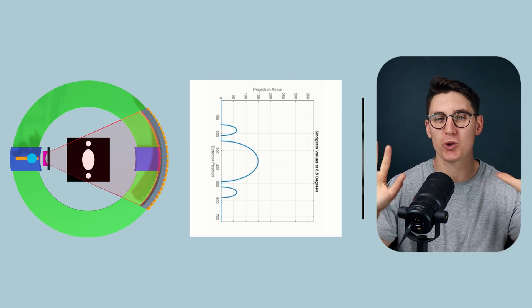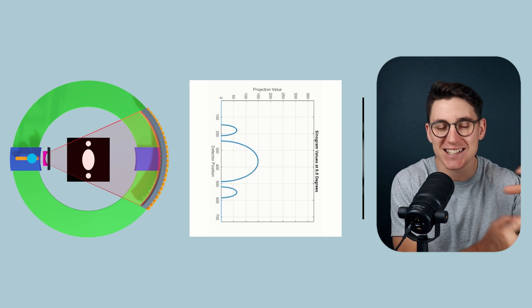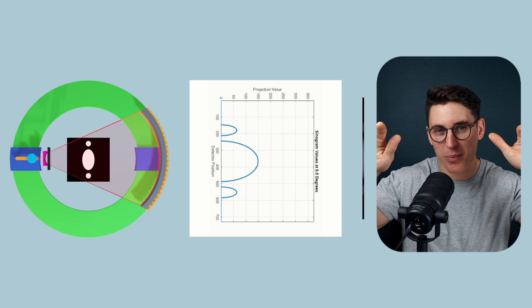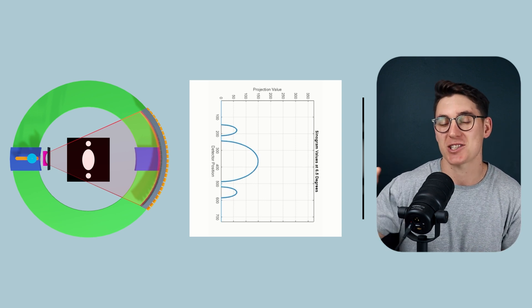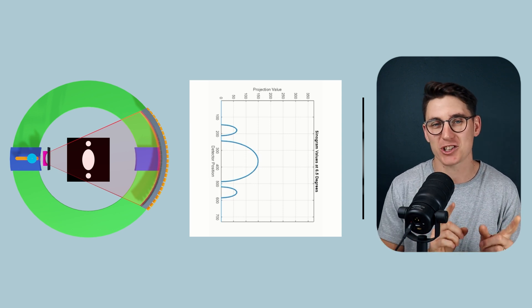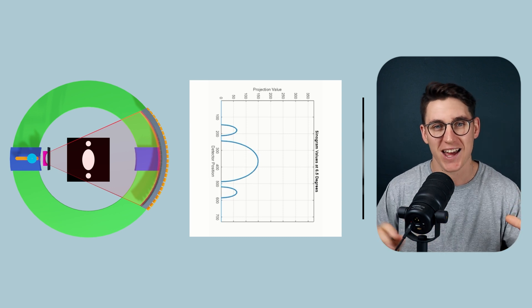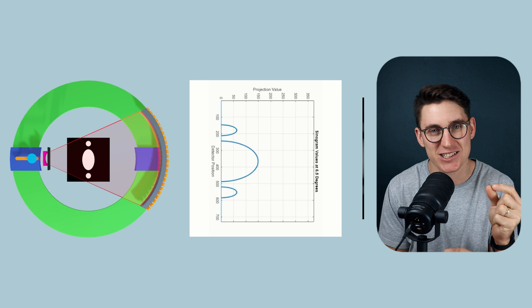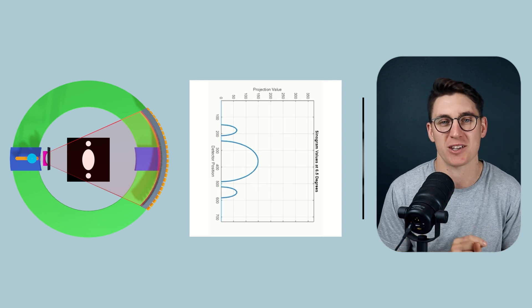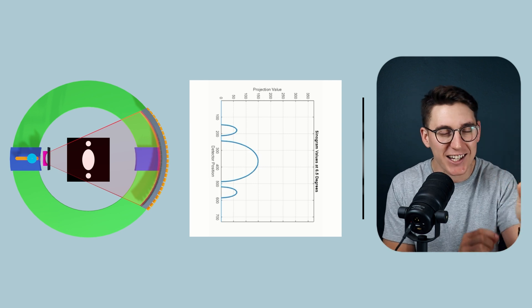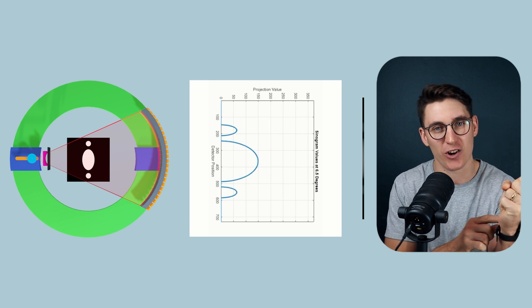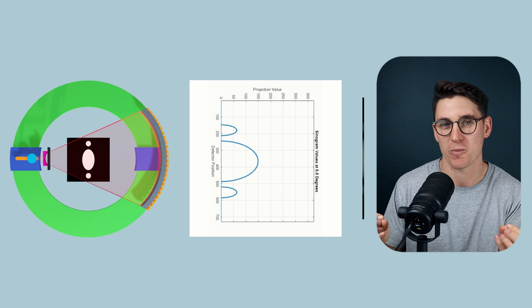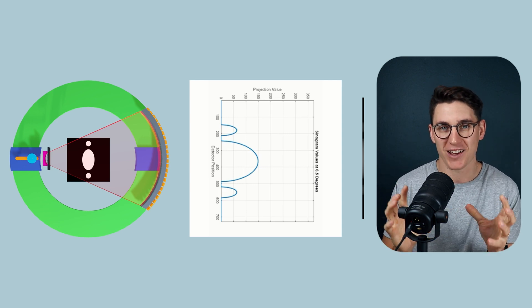Hello everybody, and welcome back. Until now, we've focused on two core concepts in CT physics. The first has been centered around data acquisition, and the second has been looking at image display — how we allocate a Hounsfield unit to each pixel within our image and then apply a grayscale window to those Hounsfield units to display a grayscale 2D image we can interpret. What we're going to be looking at in the next few talks is the link between these two concepts: how we take the initial projection data and figure out the attenuation value for different spatial locations — voxels — within our patient, convert that to Hounsfield units, and ultimately display the image. So how do we go about calculating that attenuation data?